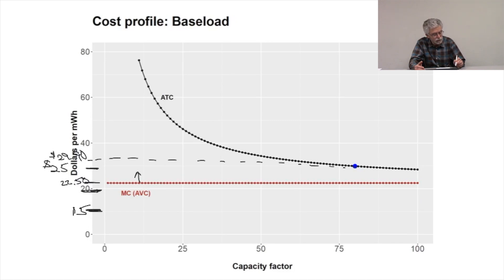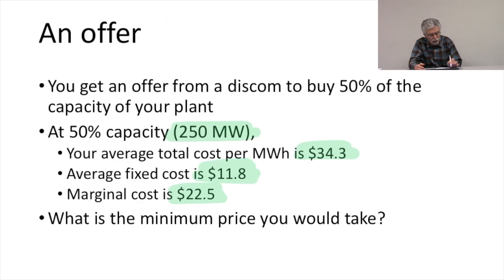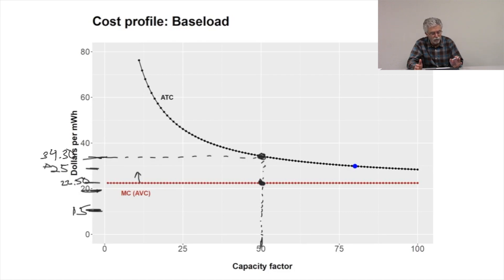I need to clarify: we're only contracting for 50%, so remember our marginal cost is $22.50, but our average total cost at 50% capacity is $34.30. So we have an outstanding offer — the best we can do — of $25 per megawatt hour, where the variable costs are $22.50 but our long run average cost is $34.30. The question is: should we run the plant?